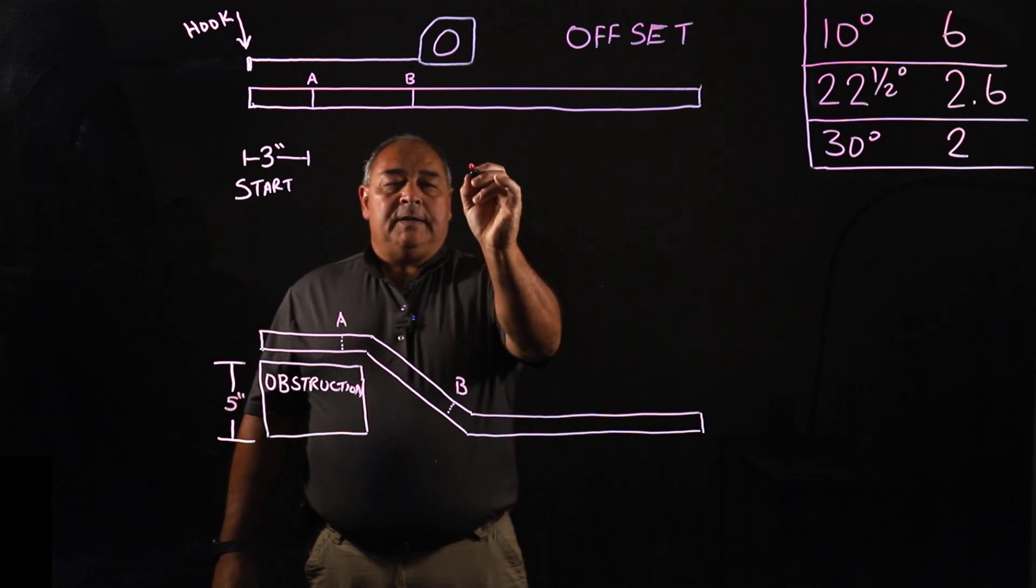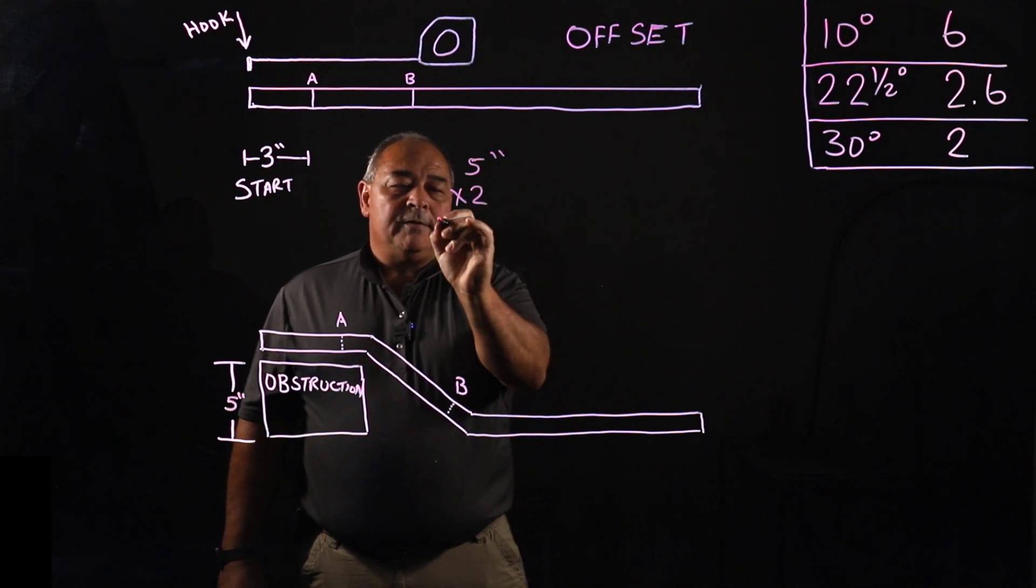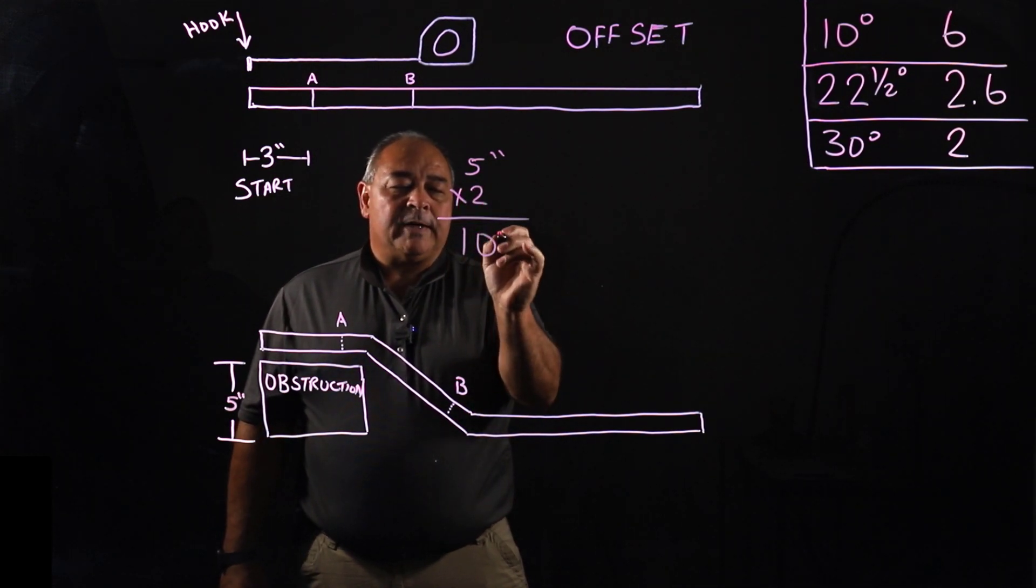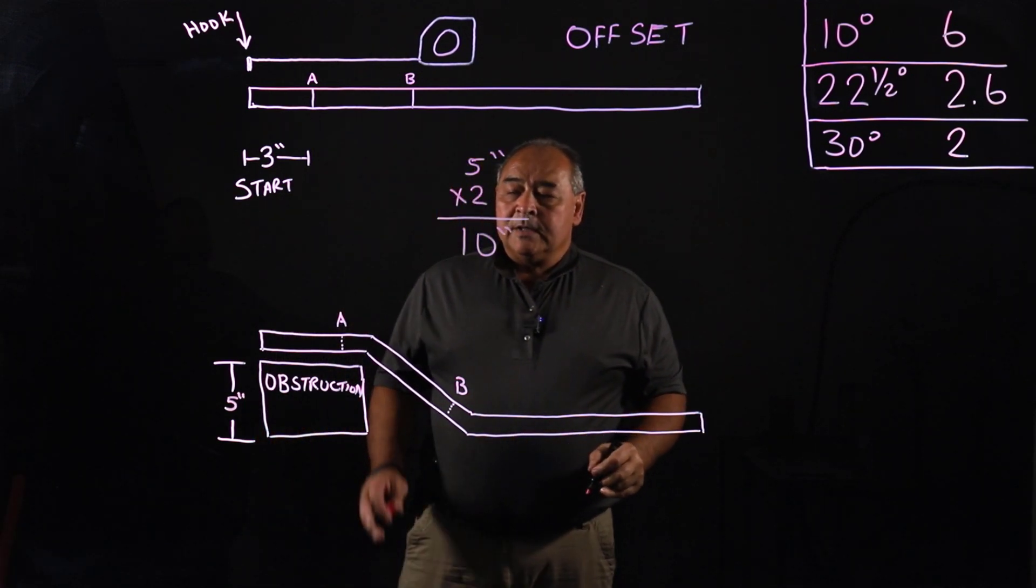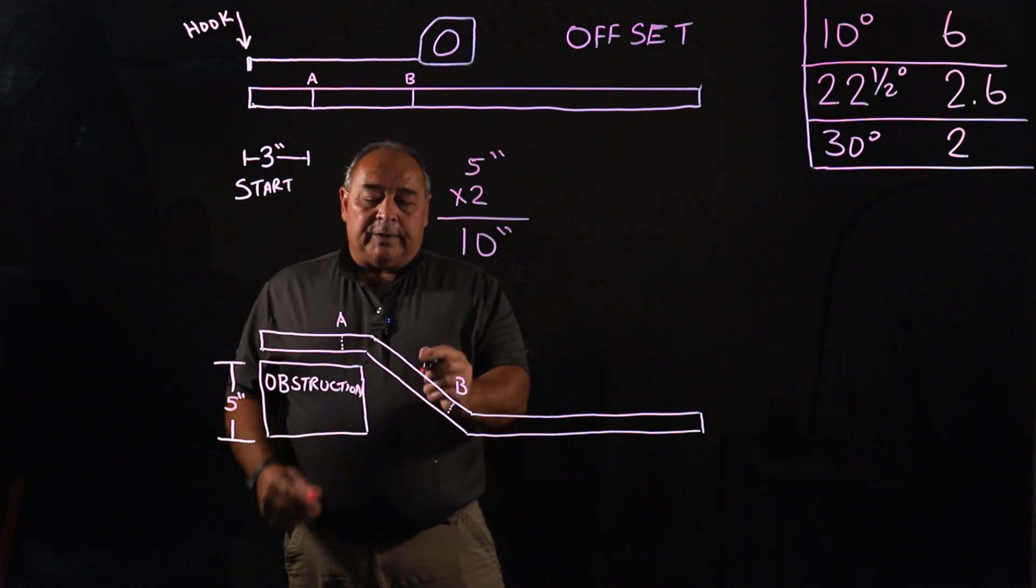So the math would look like this: 5 inches times 2. Well, obviously that's very simple, you didn't even have to write that down. Equals 10 inches. So from A to B, our marks would be 10 inches for a 30 degree offset.